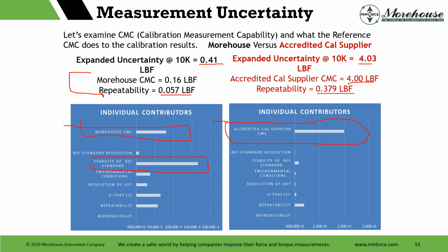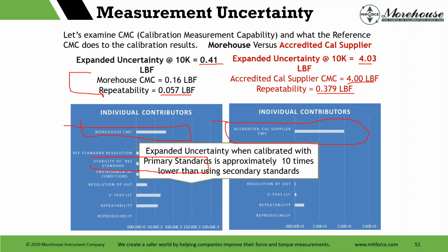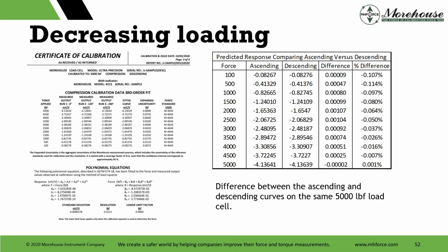So what really happens here is the starting point's a lot higher, and therefore your uncertainty is higher. Your expanded uncertainty when calibrated with primary standards is approximately 10 times lower than using secondary standards on good load cells. On load cells that aren't as repeatable, it can be 20 times lower. It can be all kinds of multiples. As much as I want to keep talking about primary standards and calibrations Morehouse offers, it's easy to me. You get better results when you use standards with lower uncertainties.